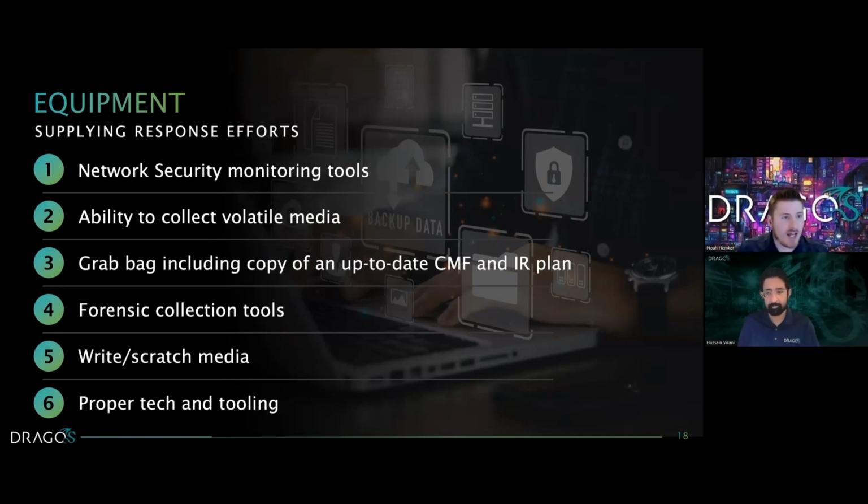One thing to highlight here when we talk about IT and OT differences: generally in IT, you'd say, okay, let me install an agent, let me scale my operations. With OT, like we spoke before, you can't change that baseline of that SCADA system. You need to stick within scope or not install anything. So generally that results in scripts that can be run from a drive that then will collect the forensic evidence so you can take it back and analyze it offline. Or you can throw it online, but you definitely can't have an active connection to those systems to collect that data.